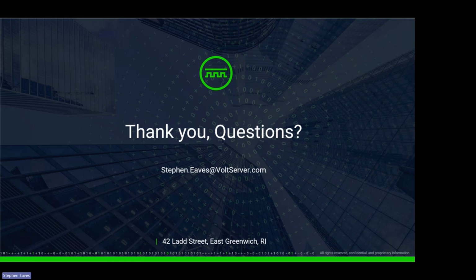Yeah, no, I completely understand. It depends how it's done. I have to say, if it's done without any energy storage... one option is to have batteries that take peak loads, which could be useful for things like stoves, but not for long durations of heating on the heat pump side. But with load management, whatever the impact would normally be with what I call the brute force method—upgrading all the panel boxes to 200 amps in the apartments—it's maybe half to a quarter of the impact on the service entrance.